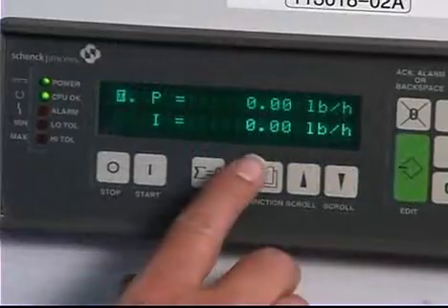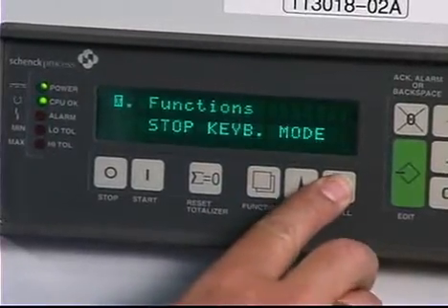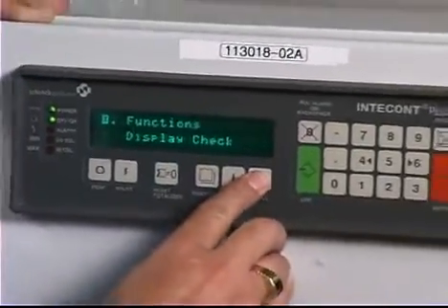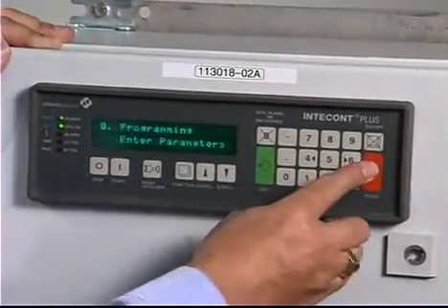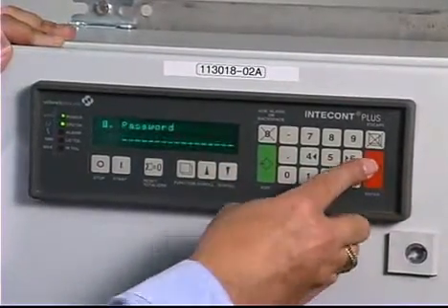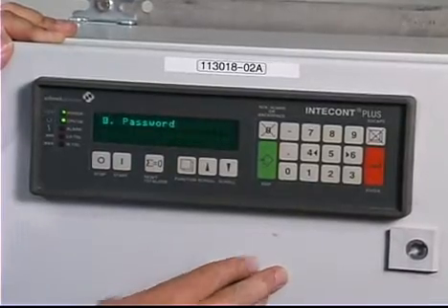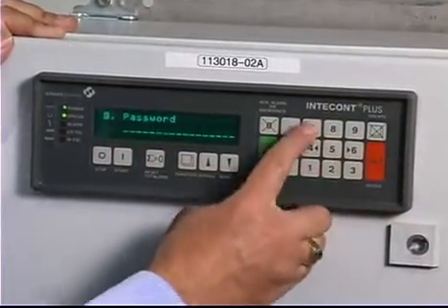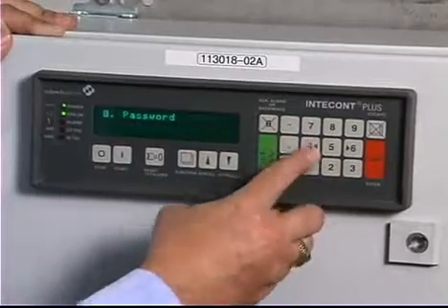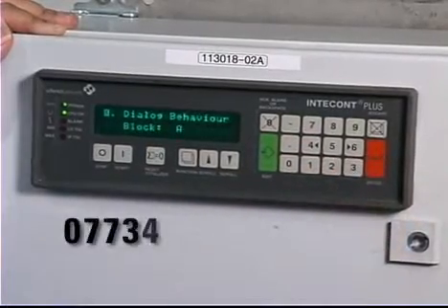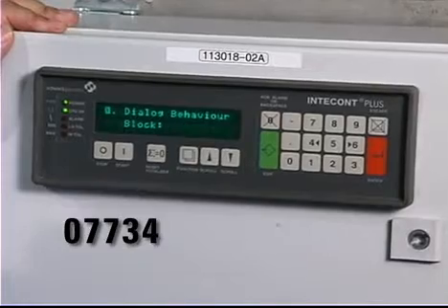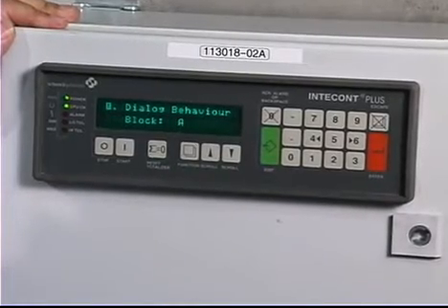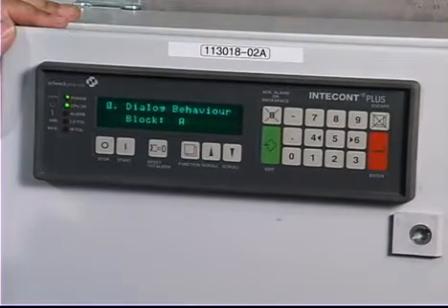To begin entering data, press the Function key and use the scroll buttons to select the programming menu. The Enter key puts you in the programming menu, where you'll scroll to select Enter Parameters. The system prompts for a password. Use the default password 07734. This is the main parameters menu, where the system information is entered for successful setup. The numbers entered in this video are for demonstration only. The actual numbers you enter in a particular installation may vary.